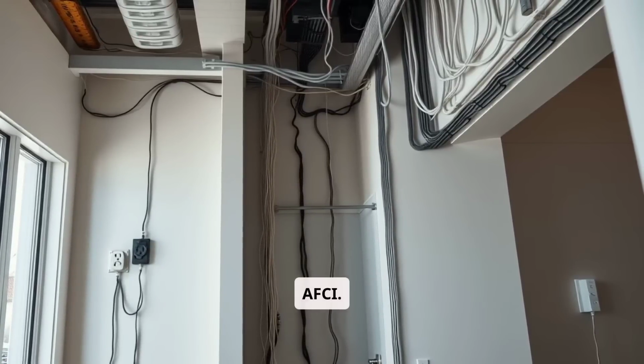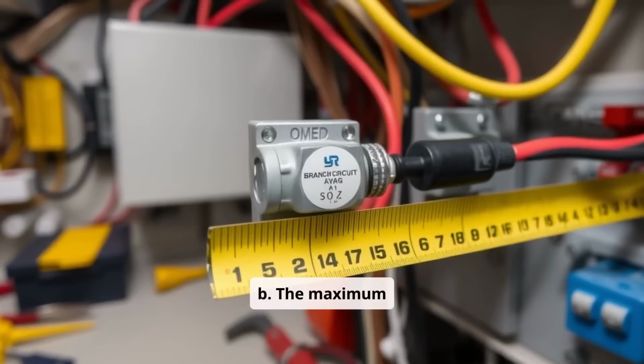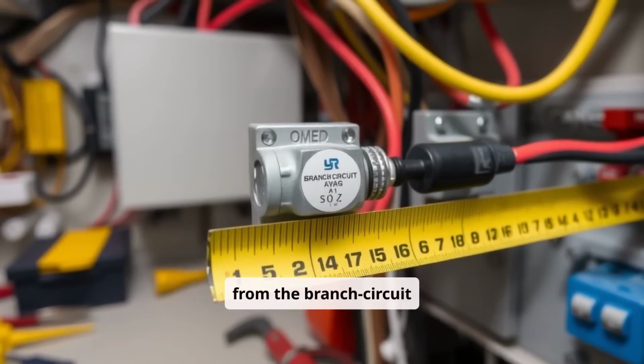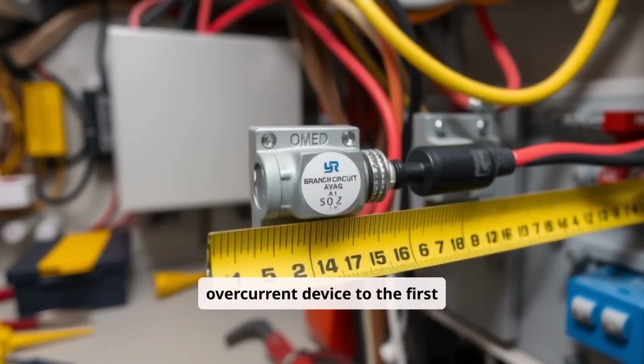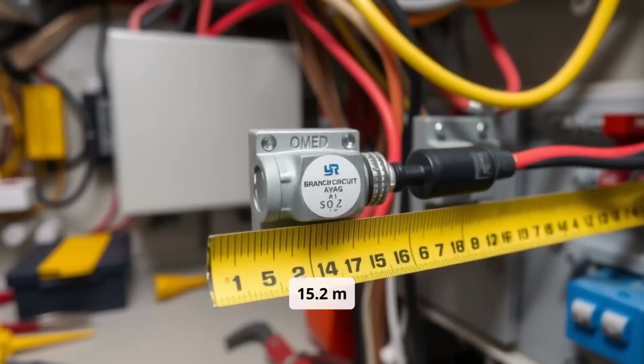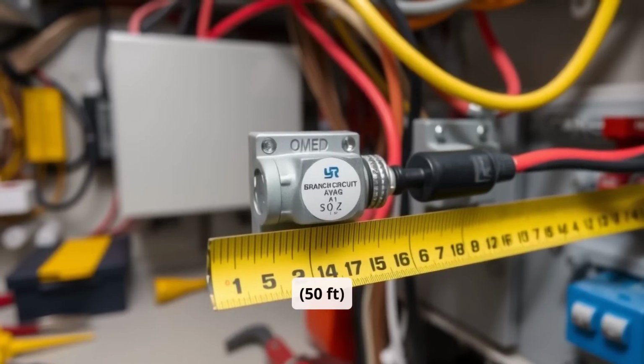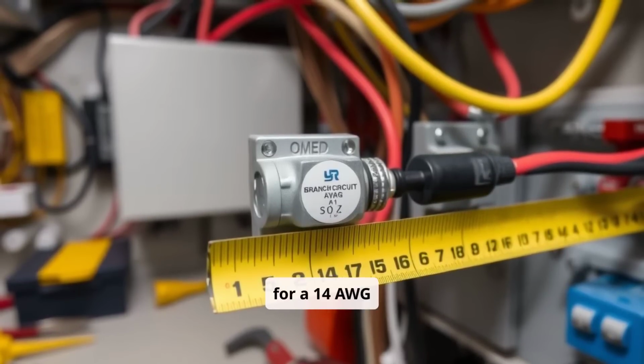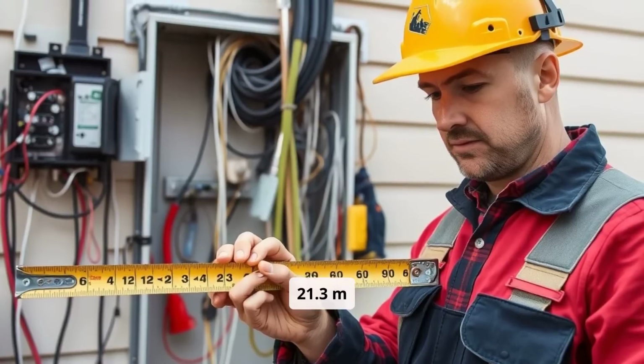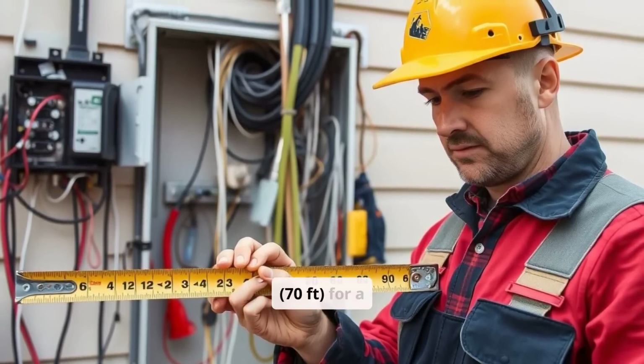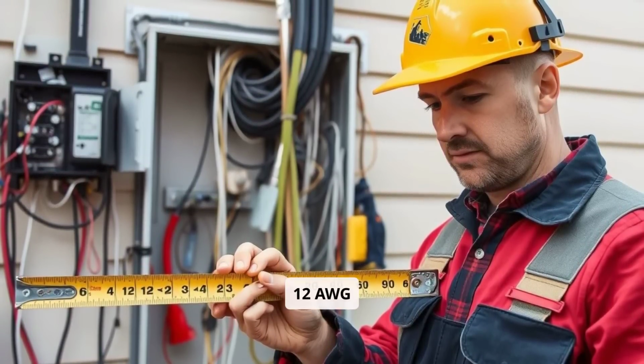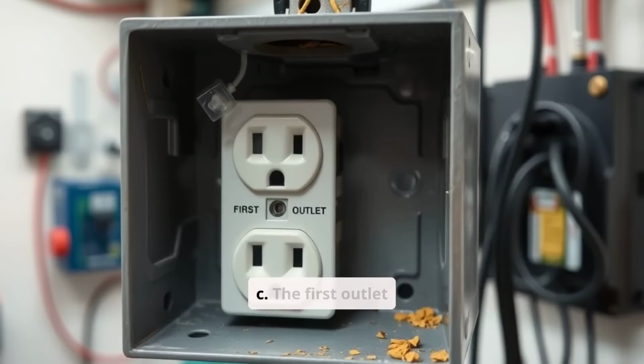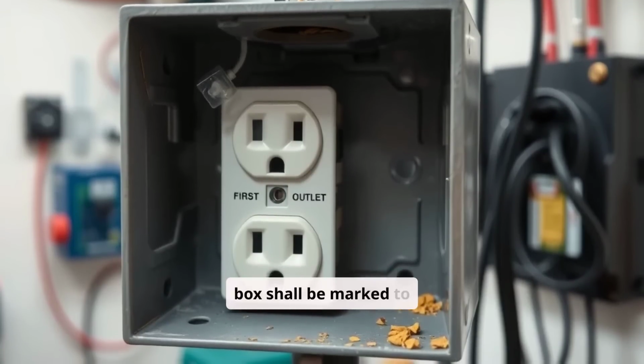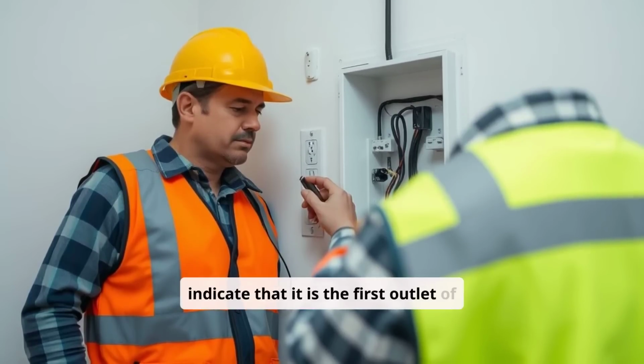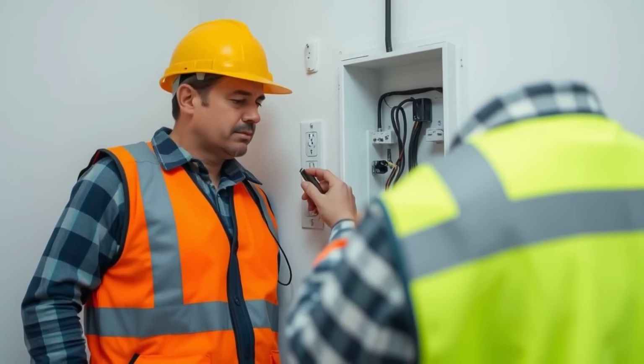B. The maximum length of the branch circuit wiring from the branch circuit overcurrent device to the first outlet shall not exceed 15.2 meters, 50 feet, for a 14 AWG conductor or 21.3 meters, 70 feet, for a 12 AWG conductor. C. The first outlet box shall be marked to indicate that it is the first outlet of the branch circuit.